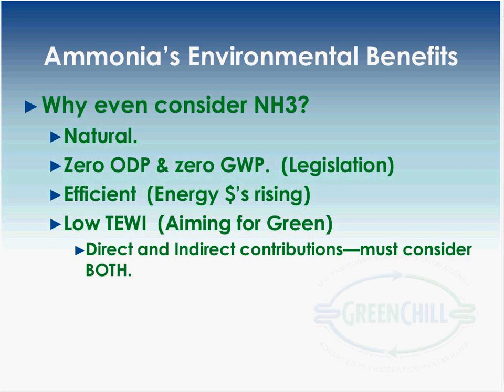There's the case where you go into an existing store and put in all the direct expansion racks, pull the HFC back into the compressor room, and limit your HFC charge with a secondary system. If you're not careful, you could end up in a worse scenario environmentally than you started with, if your pumping costs make the system less efficient, since most of your footprint contribution can come from the energy side.